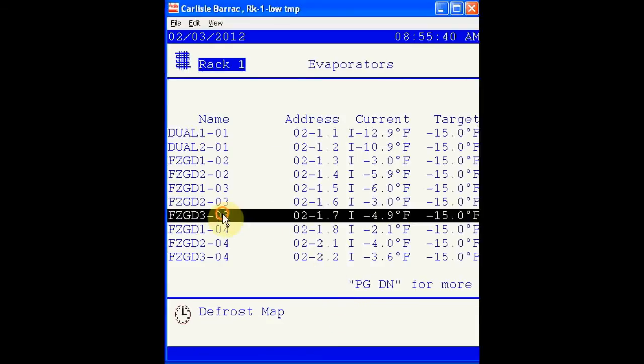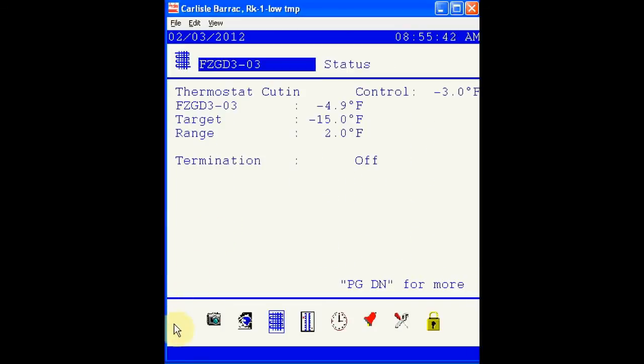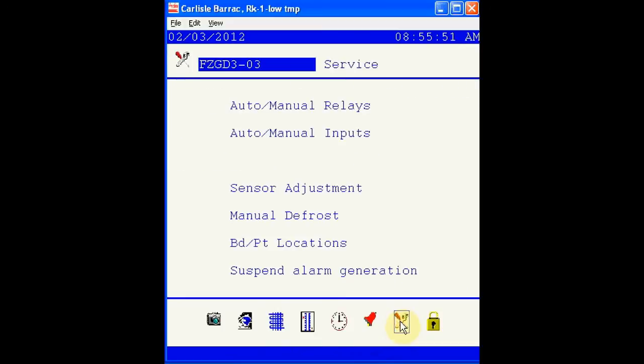Let's select a sensor. As you can see, once again, you have several options available at the bottom of your screen with icons. Let's go back to the service icon to see what's available. Here we can auto manual relays, auto manual digital inputs, offset and adjust sensors, put cases in manual defrost, view or change board points, or suspend alarms. Suspending alarms is done on a per sensor basis. For instance, if a case has 3 sensors and you override one sensor, only that sensor would be affected.